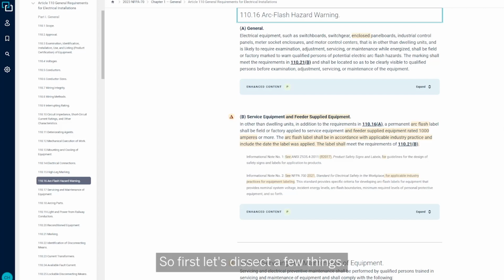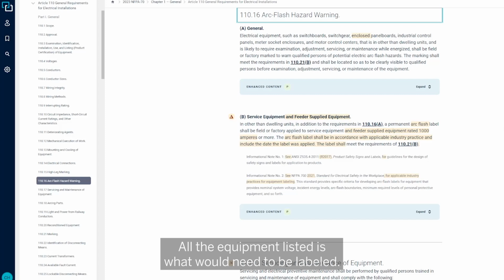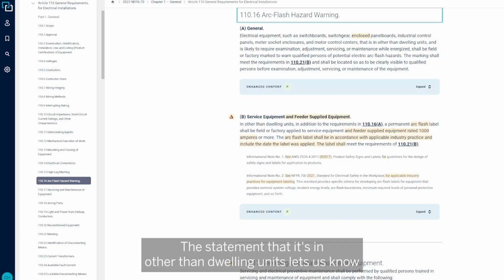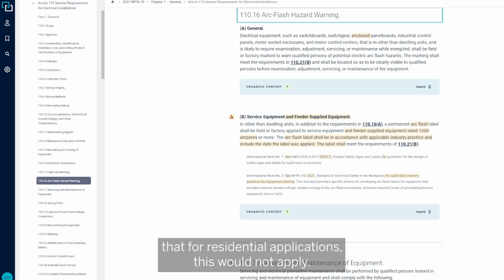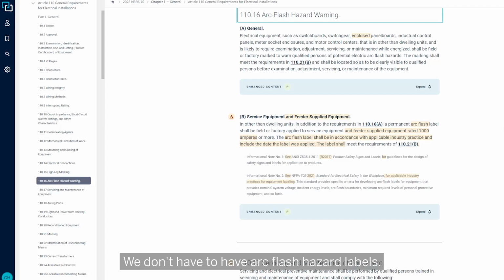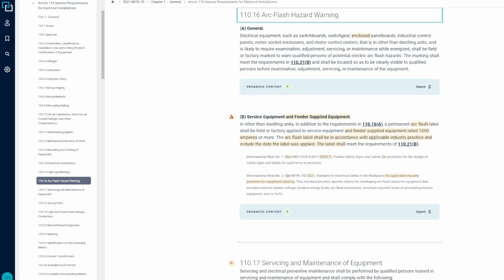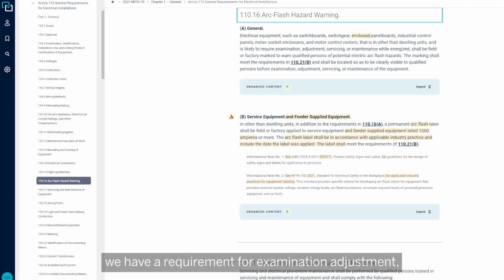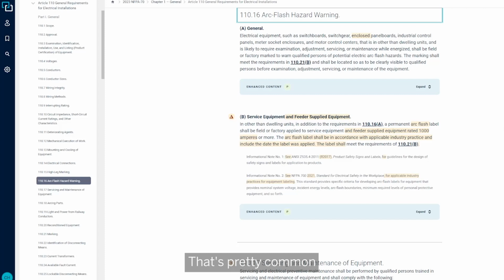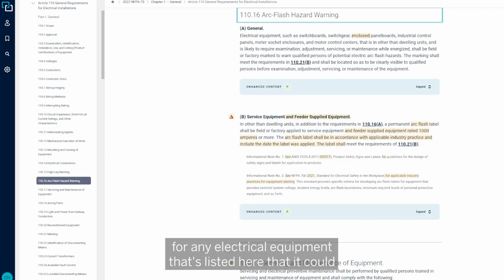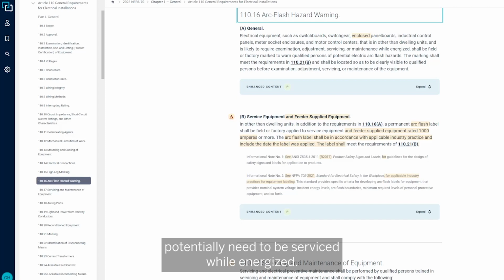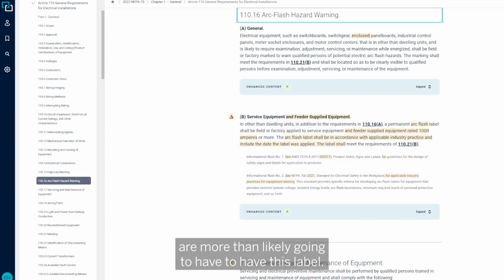So first, let's dissect a few things. All the equipment listed is what would need to be labeled, so it gives us a good idea there. The statement that it's in other than dwelling units lets us know that for residential applications, this would not apply. We don't have to have arc flash hazard labels. Now, in looking further into this, we have a requirement for examination, adjustment, servicing, or maintenance while energized. That's pretty common for any electrical equipment that's listed here, that it could potentially need to be serviced while energized. So we need to keep that in mind. Any of these electrical pieces of equipment are more than likely going to have this label.